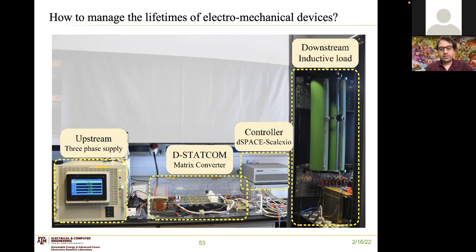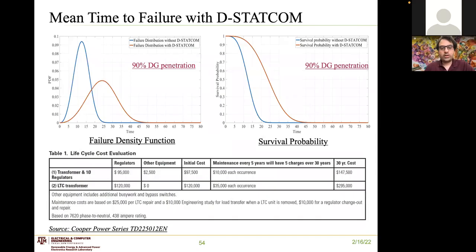When we consider a DStatCom in our network and redo the failure analysis, on the left we have the density functions plotted with and without the DStatCom. The blue curve is without it and the red curve is with it, considering 90% penetration of DG. With the DStatCom, not only are we extending the lifespans of these devices, but the probability of failure also drops.